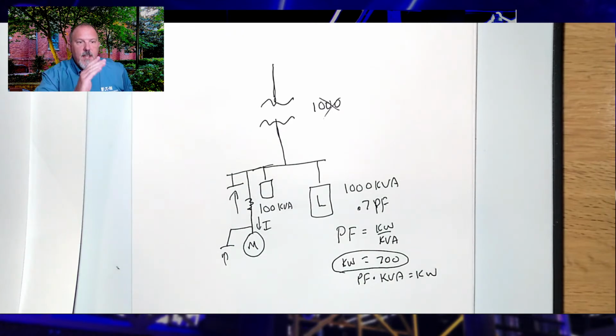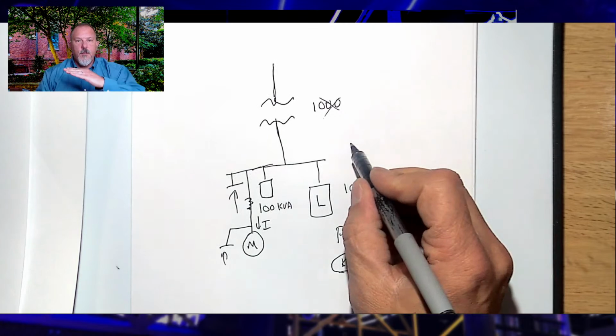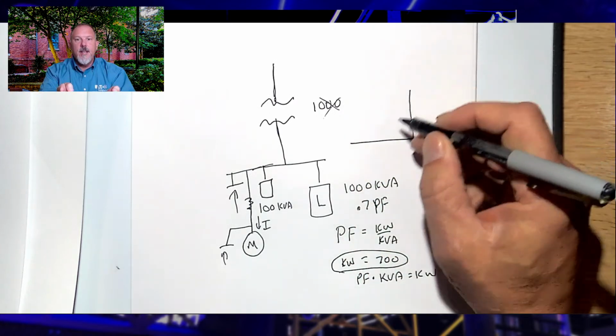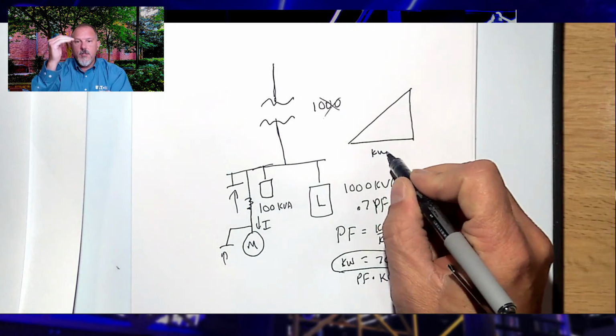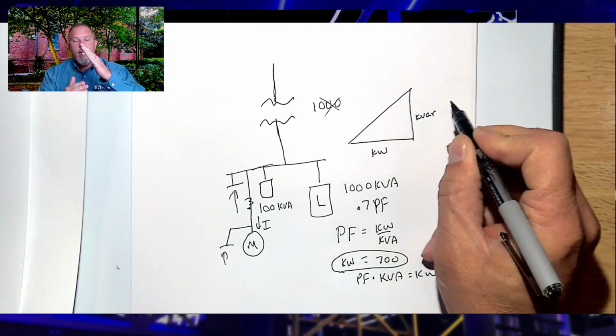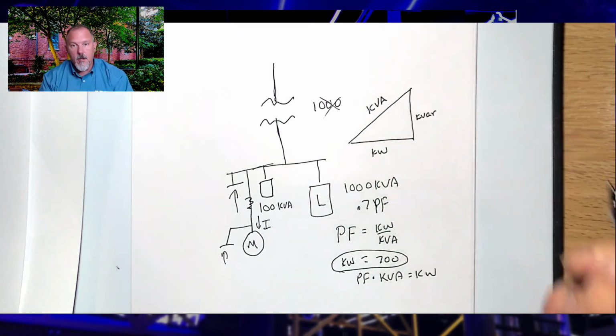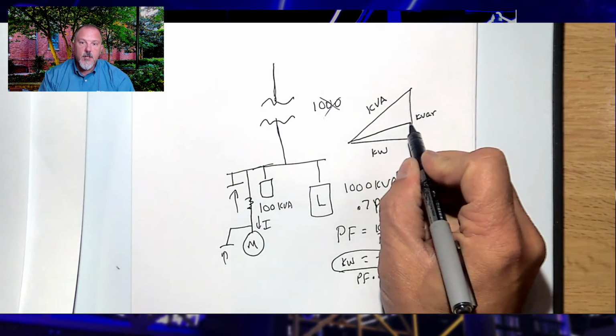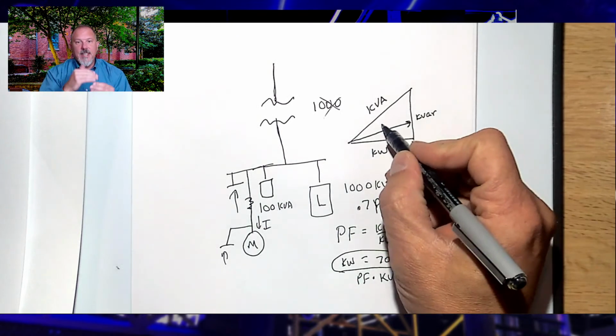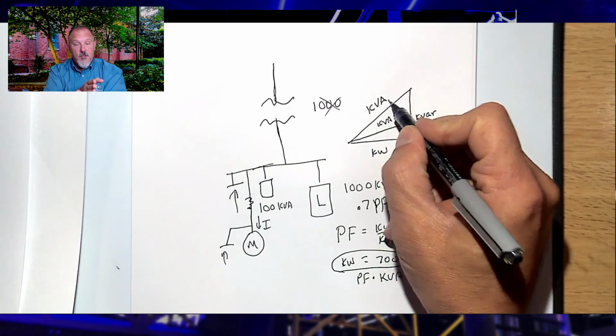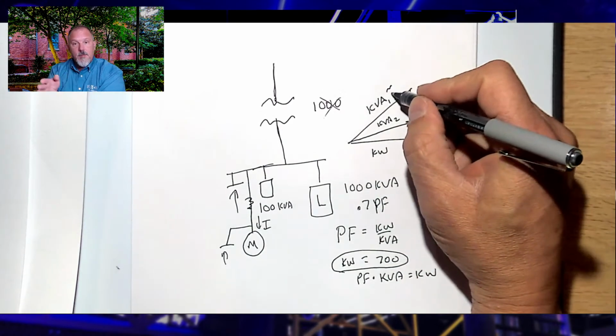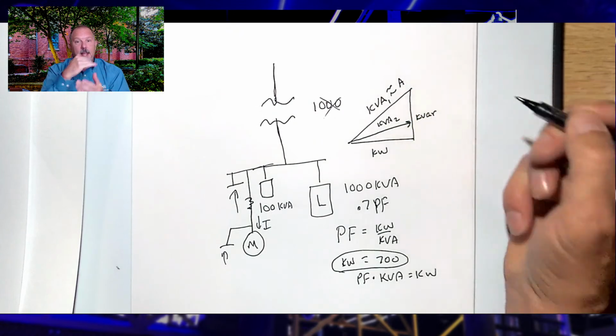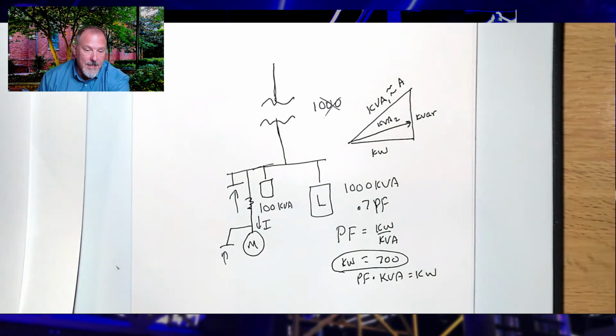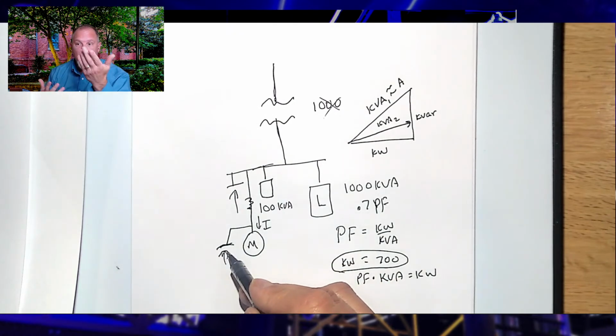Yeah. So kVA is the hypotenuse of the triangle. If you're horizontal, that's your kilowatts, that's your VARs, and there's your kVA. So if I reduce the VARs, my kVA is lower because the angle is smaller. By reducing the kilovars, my kVA comes down, which means the amps come down, because kVA is proportional to amps. But to your point, if I put that down at the motor, I can reduce my losses. But that's not a lot of losses. You've got to think about it.